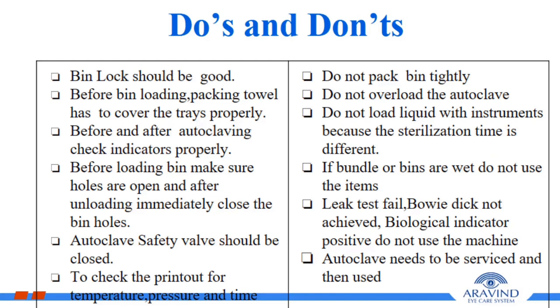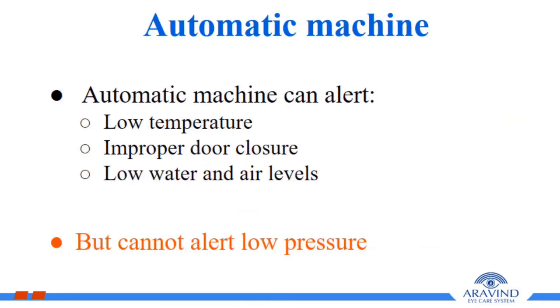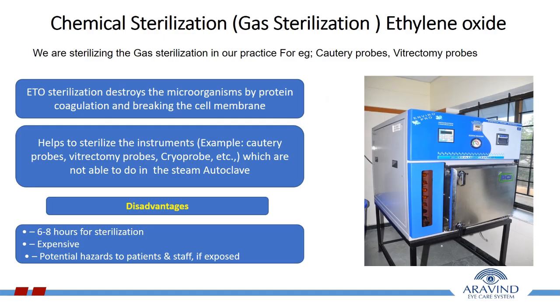Several do's and don'ts that are to be followed strictly while performing the procedure of autoclave are listed. The machine is completely automatic and will give an alarm in case of low temperatures, improper door closure, low water and air levels achieved inside the inner chamber, but it will not give an alarm in case of low pressures.